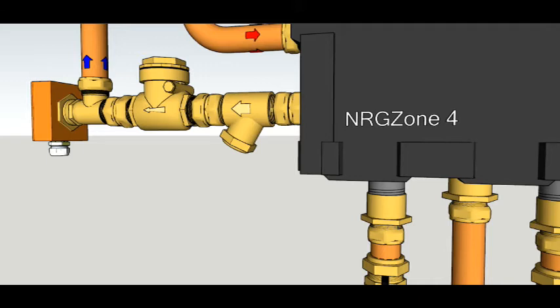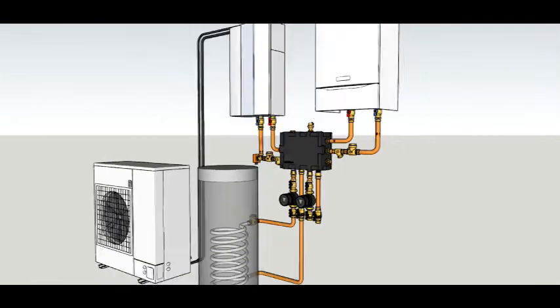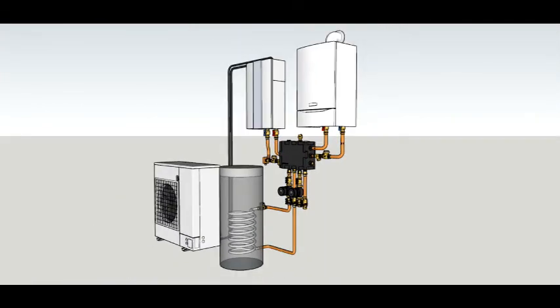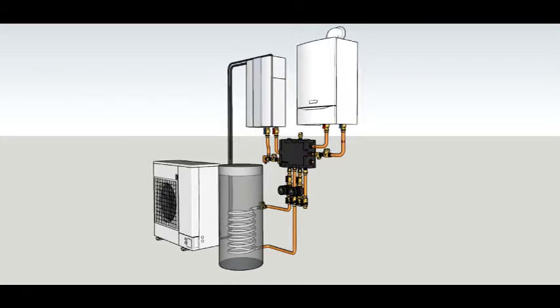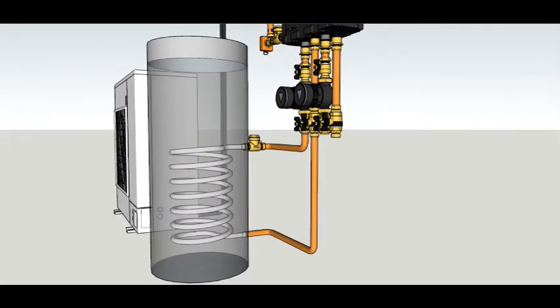We put a domestic hot water cylinder on the pair of connections underneath the manifold with pump on the left, the return coming in beside it on the right. From the pump it goes through a non-return valve which is the connection to the cylinder. Once the cylinder is hot, you don't want heat drifting back out and up through the pipework and through the manifold, losing or dissipating the heat that you've just stored in the cylinder.